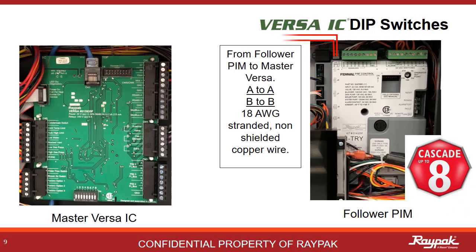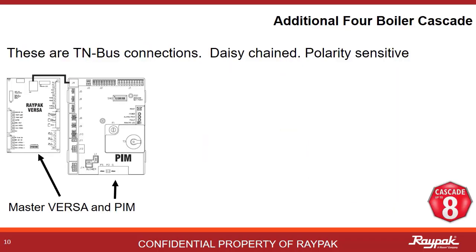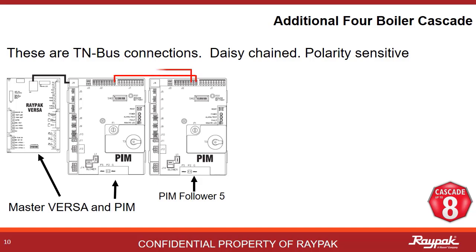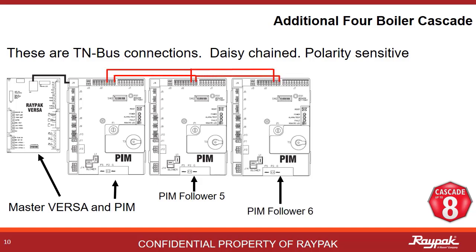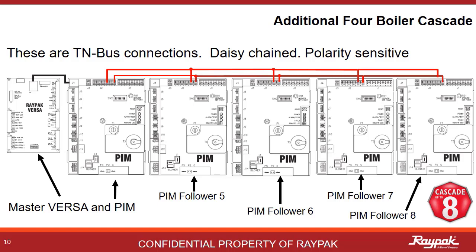The first three followers connect from each follower PIM to the master Versa on the FT bus. Always use 18 gauge stranded non-shielded copper wire for these connections. With the new software, four additional follower PIMs can be connected to the master PIM. These four additional followers will be called follower five, six, seven, and eight. They will wire up PIM to PIM in a daisy chain fashion. This connection is called a TN bus.